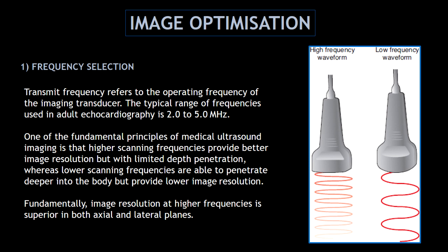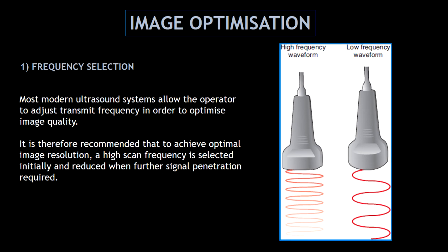The first feature we can adjust to optimize the image is changing the frequency of the transducer. The transmit frequency refers to the operating frequency of the imaging transducer. If you increase the frequency, you will get a better image resolution, but with limited depth penetration. Lower scanning frequencies are able to penetrate deeper into the body, but provide lower image resolution. Image resolution at higher frequencies is superior in both axial and lateral planes. It's recommended to select a high scan frequency initially and reduce it when further signal penetration is required.